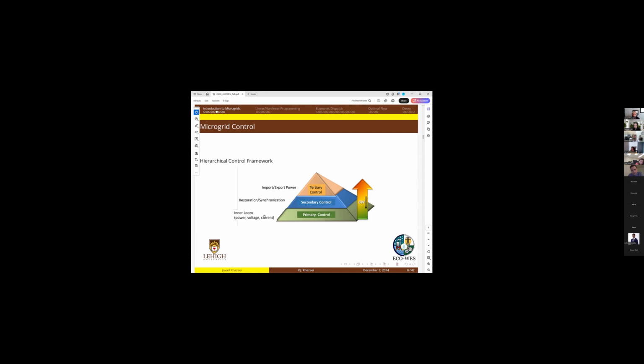And I have examples to show what these controllers are. This is usually 10 to 15 times slower than the primary controller. Again, you're looking at tens or hundreds of milliseconds for these two controllers, and these two controllers are at the local level. That means if you buy an inverter-based resource off the shelf, it already comes with these two controllers implemented. What you would do is control at the tertiary level. That would be the set points that you would set for this converter or distributed energy resource to control the amount of active and reactive power that you're getting from this unit. And this is the level that we are going to focus on today.